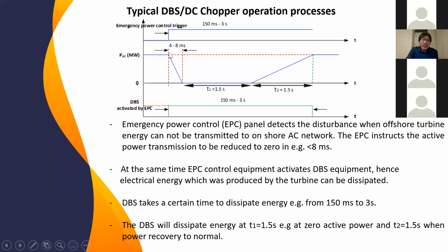Imagine, the EPC will instruct a converter or turbine to stop, let's say within 4 to 8 milliseconds. And at the same time, EPC will instruct the DBS, dynamic braking system or DC chopper, to absorb the energy. So when the energy goes down from 1 PU to 0, where should the energy be dissipated?